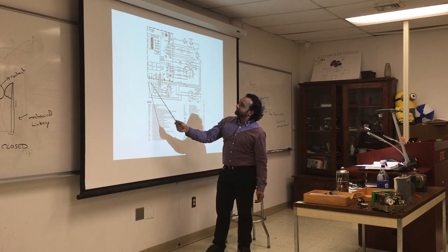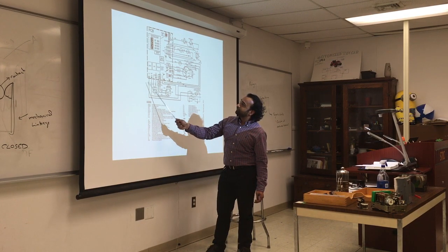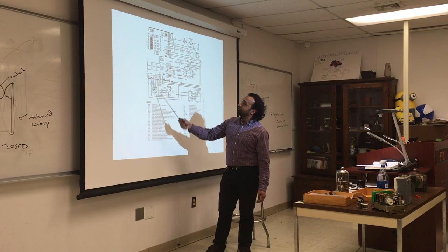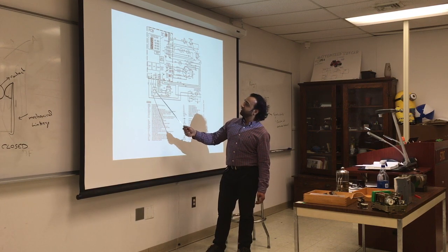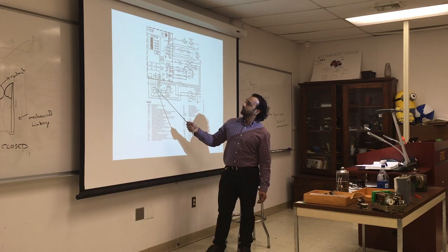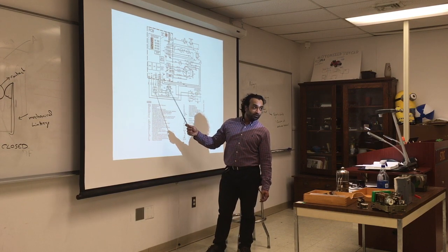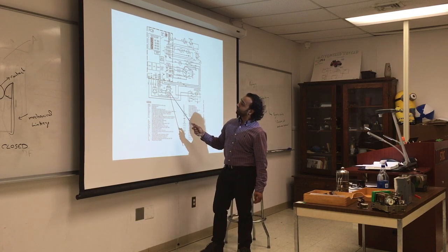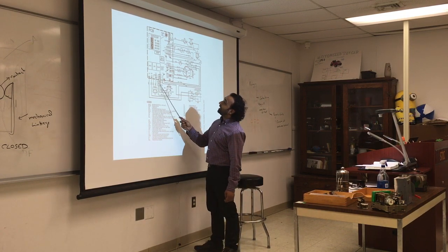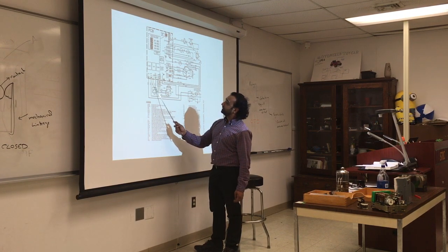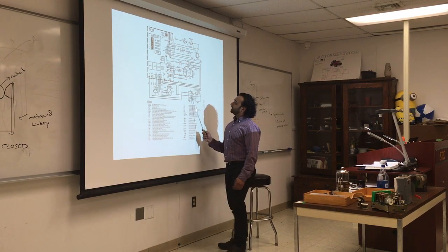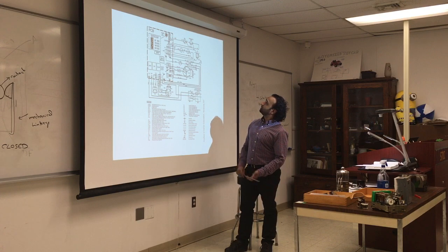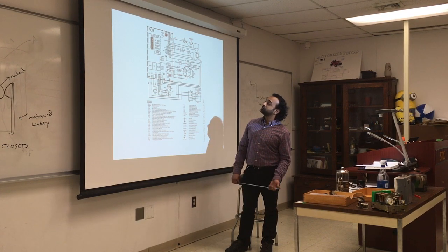What's coming out of this box? Black, black, black, line voltage. Another line voltage, three phase. Another black and neutral. So we know it's three-phase AC. White is neutral. Another three-phase is going to the motor. So this motor is going to be three-phase. I don't even have to wire the motor. It's wired already. This is my wiring, and it's going to go to the disconnect switch, and that's all. That's all you have to do.